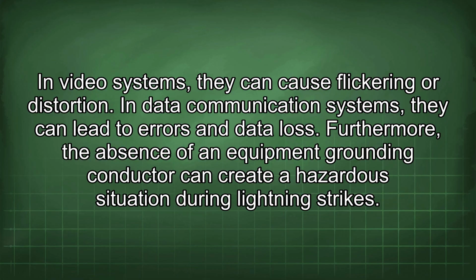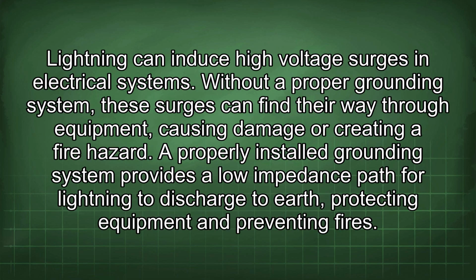Furthermore, the absence of an equipment grounding conductor can create a hazardous situation during lightning strikes. Lightning can induce high voltage surges in electrical systems. Without a proper grounding system, these surges can find their way through equipment, causing damage or creating a fire hazard. A properly installed grounding system provides a low impedance path for lightning to discharge to earth, protecting equipment and preventing fires.